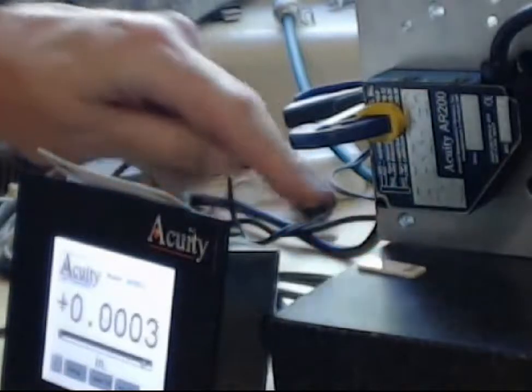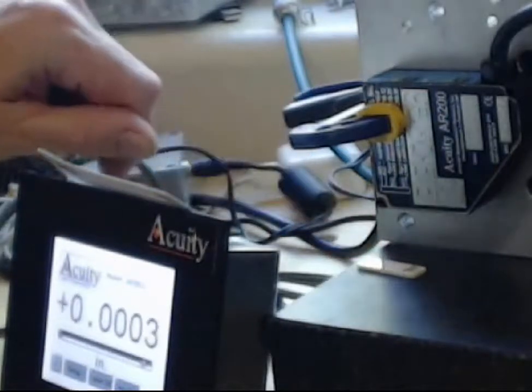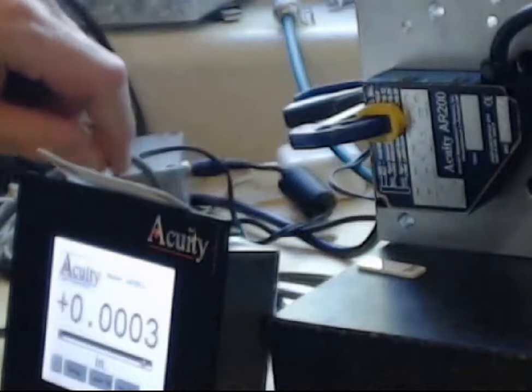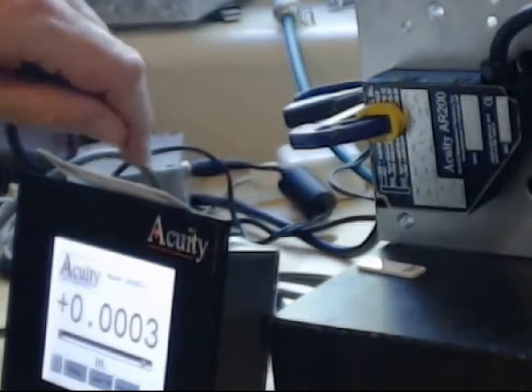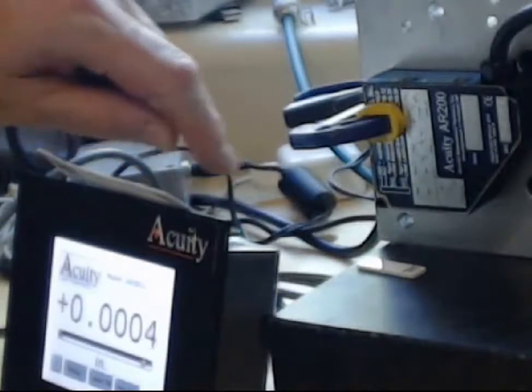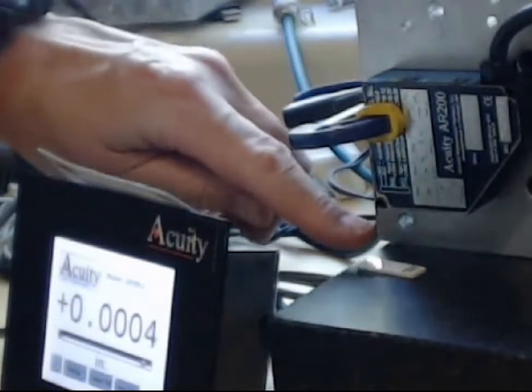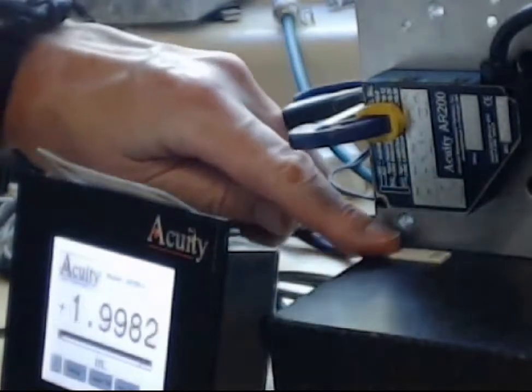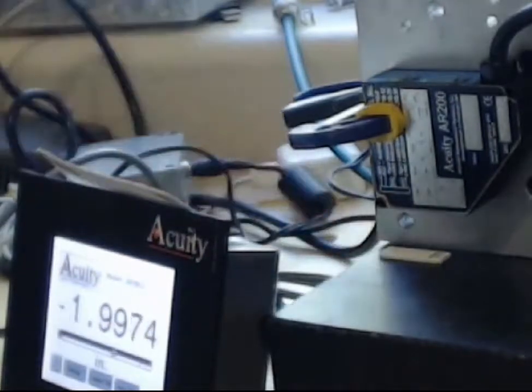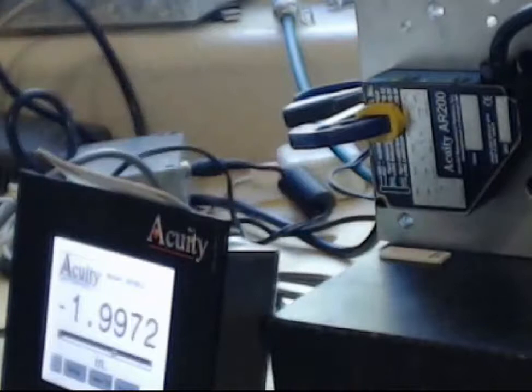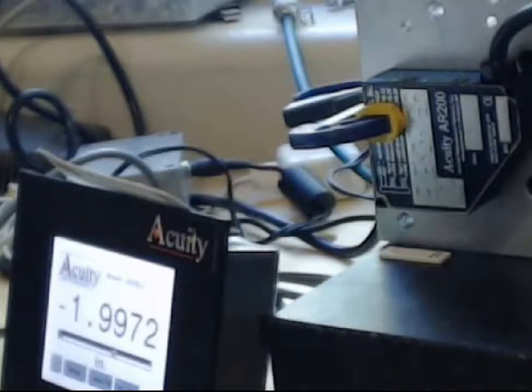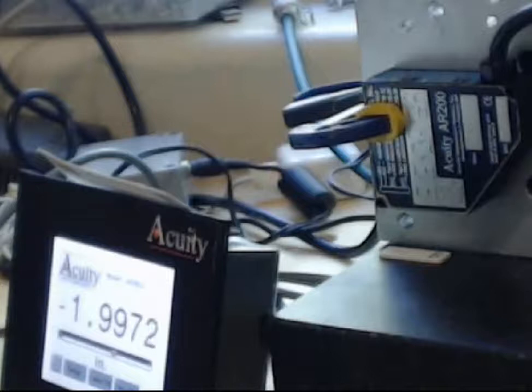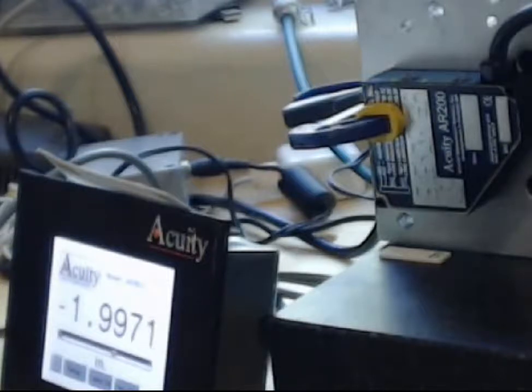And as I move it back, you can see that we're back to within 300 micro-inches, and back in here once again to within 3 microns, which is just a little over 1 ten-thousandth. So you can see that we're doing a lot better than our specs say that we are.